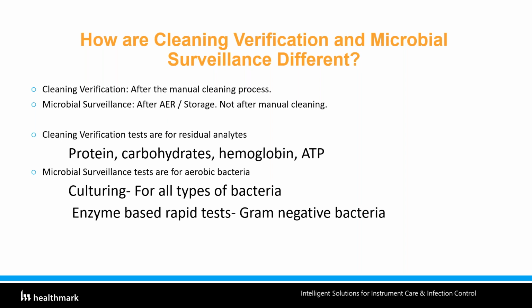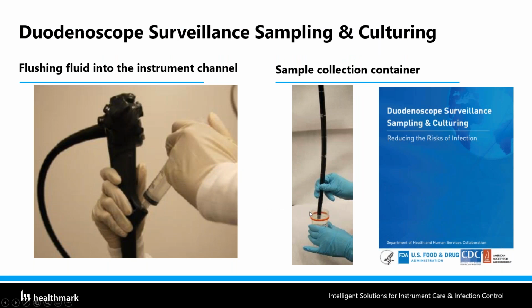So there are two different surveillance types. One is cleaning verification, which is basically after you manually clean, to just see that you cleaned it effectively. And one is microbial surveillance. This is really after the AER, or if you have it in storage, you want to see what's going on. Or if you have a contamination or cross-contamination, you can check all your scopes to see if there's something wrong with that process. For cleaning verification, you basically look for protein, carbohydrate, hemoglobin or adenosine triphosphate. But microbial surveillance is basically testing for bacteria. You basically need to culture, send it to a lab internal, or send it to an external lab, that they actually can look for bacteria, for example, the gram-negative part.